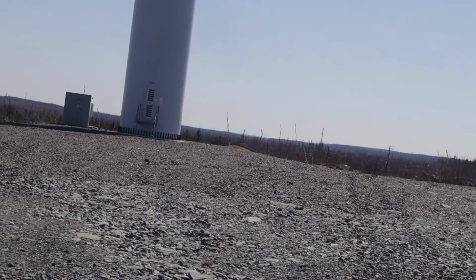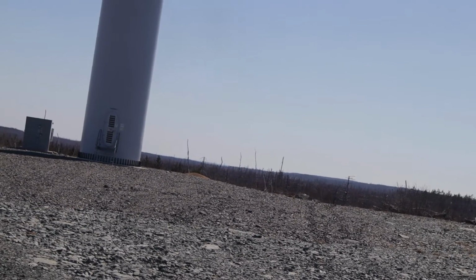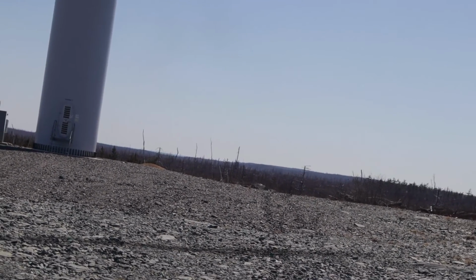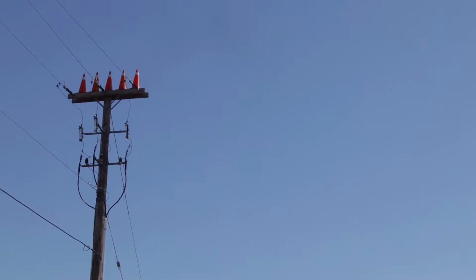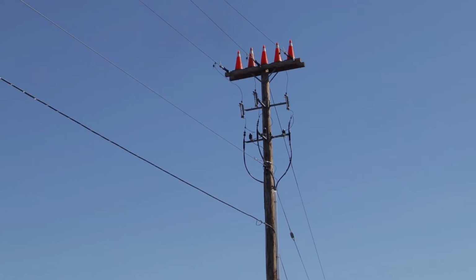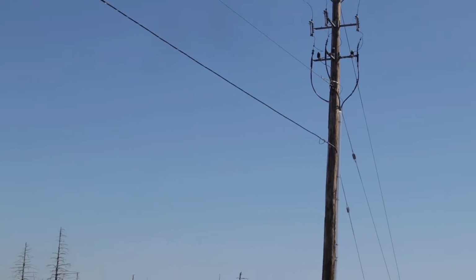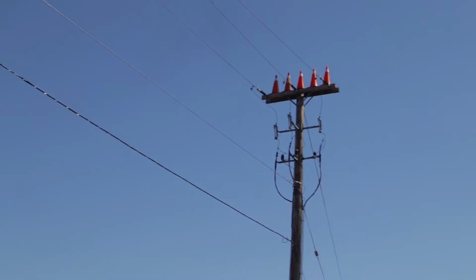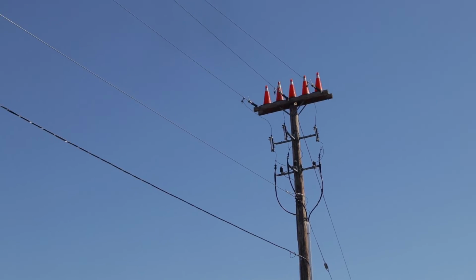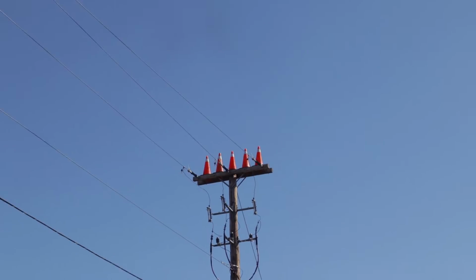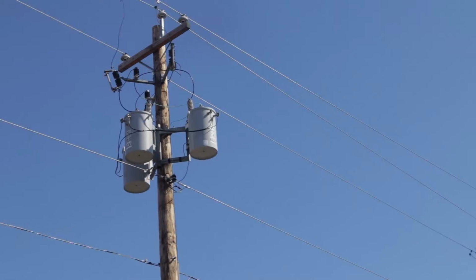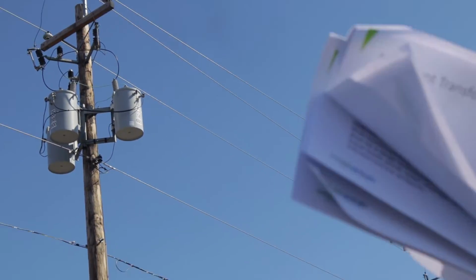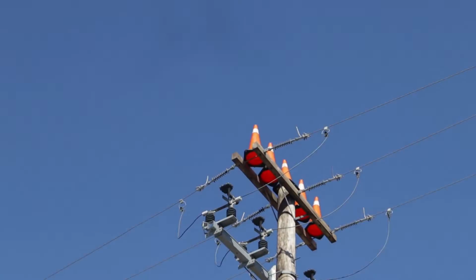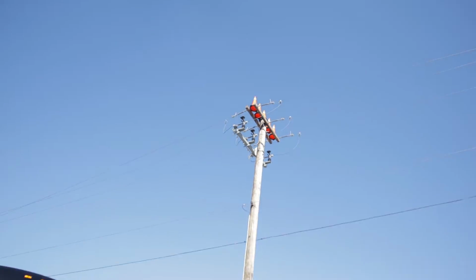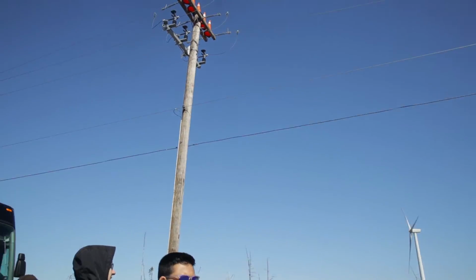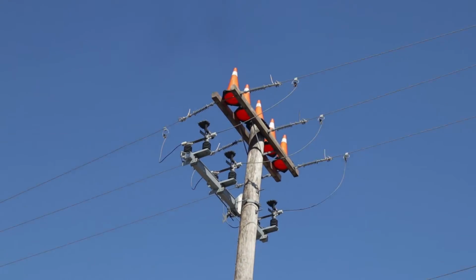Yeah, we just marched. And then basically once you leave the transformer, you go back underground to what's called the riser pole here. If they're on the utility side, they'll call it the dip pole because they're used to power going that way. Everybody in our industry calls it the riser pole because we're sending it back up. So we go through the riser pole. There's a grounding transformer that would detect ground faults, and then what's called a gang switch. The reason it's called a gang switch is because you actuate one arm on it and it opens all three phases. And so you don't single phase anything.